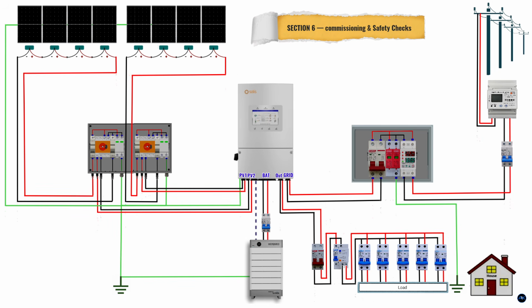Load breakers one by one. Test each circuit. Then test the RCD. Press the button. It must trip instantly. Let it run for 30 minutes. No heat, no alarms, no unusual smells. You're live.